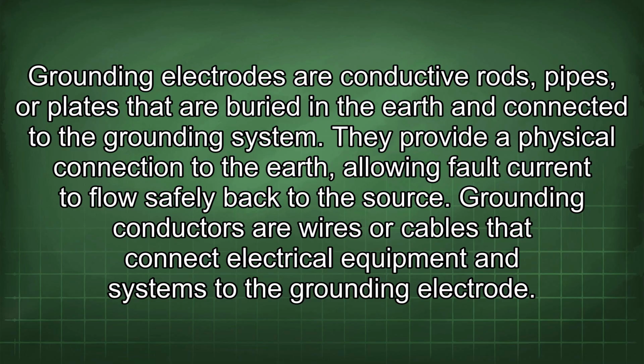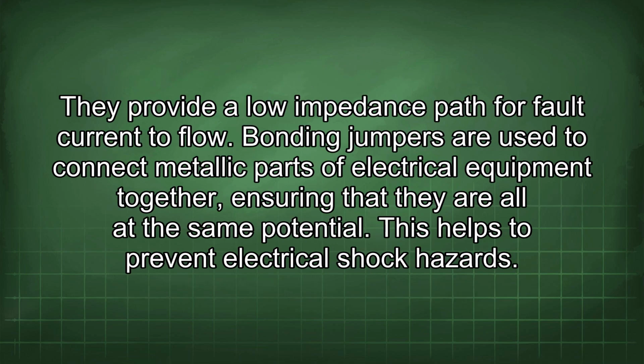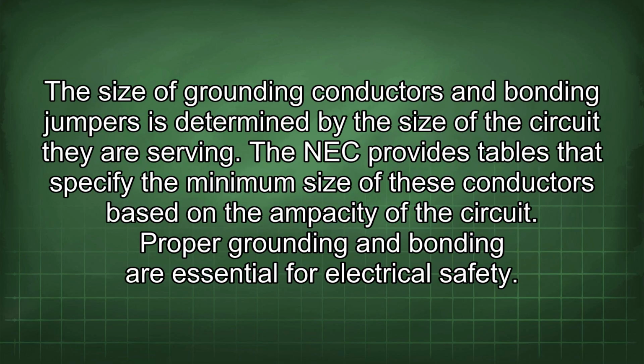Grounding conductors are wires or cables that connect electrical equipment and systems to the grounding electrode. They provide a low impedance path for fault current to flow. Bonding jumpers are used to connect metallic parts of electrical equipment together, ensuring that they are all at the same potential. This helps to prevent electrical shock hazards. The size of grounding conductors and bonding jumpers is determined by the size of the circuit they are serving. The NEC provides tables that specify the minimum size of these conductors based on the ampacity of the circuit.